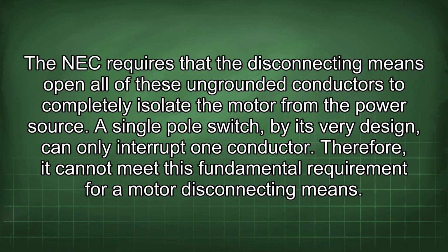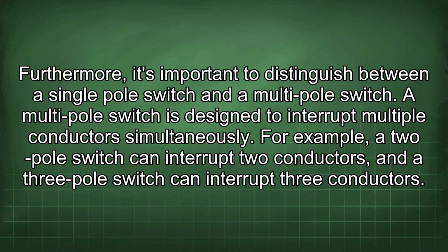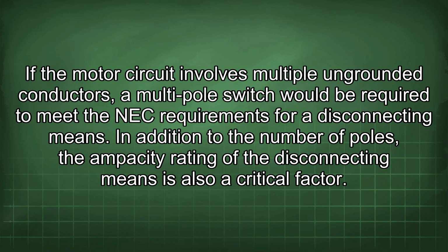power source. A single pole switch, by its very design, can only interrupt one conductor. Therefore, it cannot meet this fundamental requirement for a motor disconnecting means. Furthermore, it's important to distinguish between a single pole switch and a multi-pole switch. A multi-pole switch is designed to interrupt multiple conductors simultaneously. For example, a two-pole switch can interrupt two conductors, and a three-pole switch can interrupt three conductors.